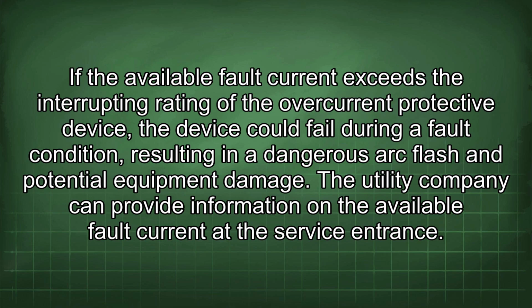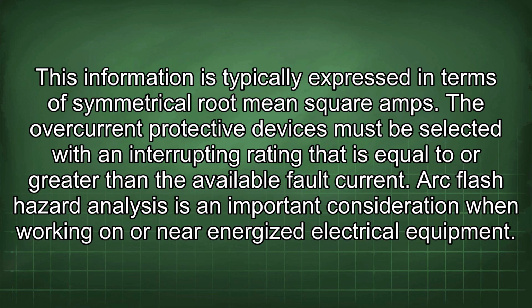The utility company can provide information on the available fault current at the service entrance. This information is typically expressed in terms of symmetrical root mean square amps. The overcurrent protective devices must be selected with an interrupting rating that is equal to or greater than the available fault current. Arc flash hazard analysis is an important consideration when working on or near energized electrical equipment.